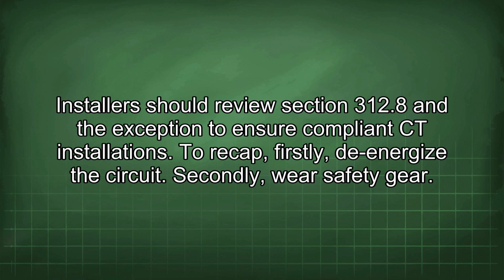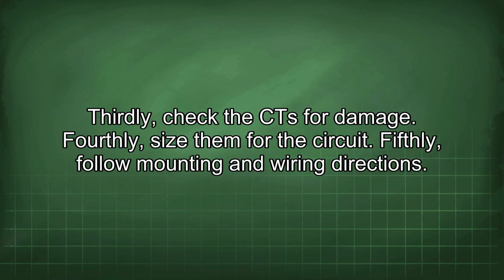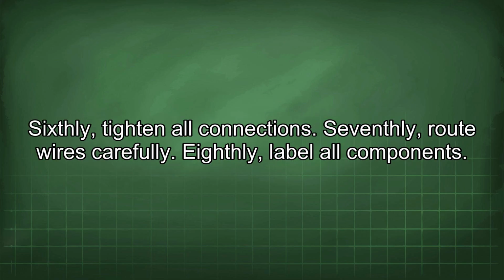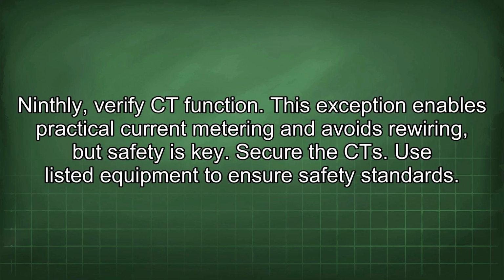To recap, firstly, de-energize the circuit. Secondly, wear safety gear. Thirdly, check the CT for damage. Fourthly, size them for the circuit. Fifthly, follow mounting and wiring directions. Sixthly, tighten all connections. Seventhly, route wires carefully. Eighthly, label all components. Ninthly, verify CT function. This exception enables practical current metering and avoids rewiring, but safety is key.